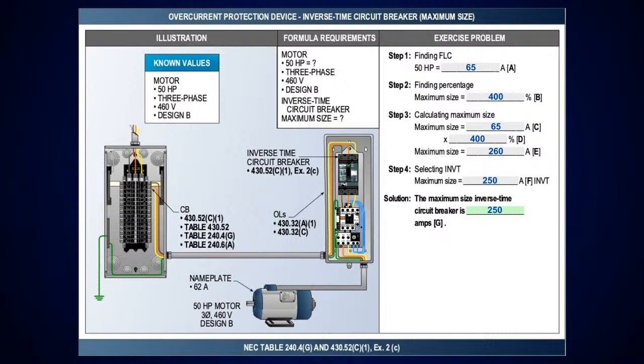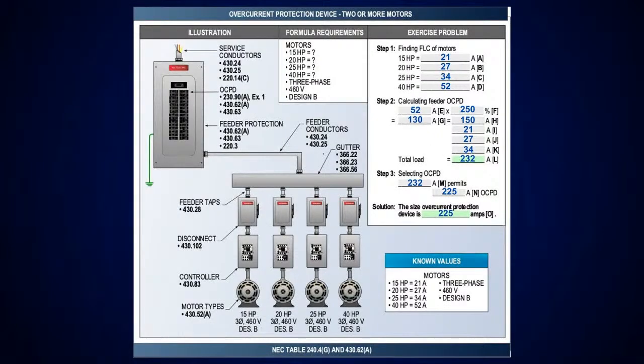Now, the next one I'm going to get into is where I have multiple motors. When you get into multiple motors, like we talked about, we used to actually have this in our publication a little bit different. We used to do the calculation and drop down to the next standard size, add them up, and then go up to the next standard size. Well, the code making panel came in and said, no, we want to do it this way. We want to calculate it, go up to the next standard size, add them up, and then drop down. Okay.